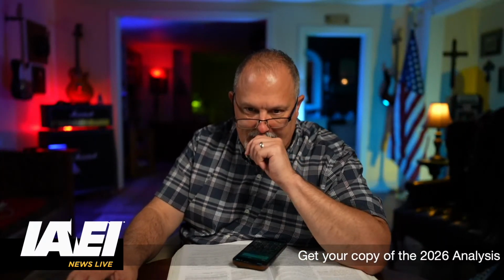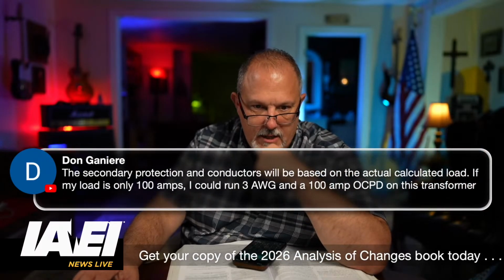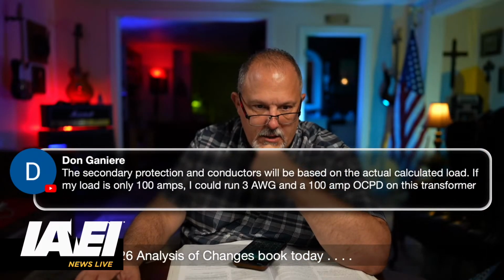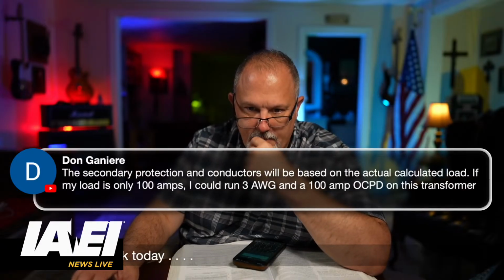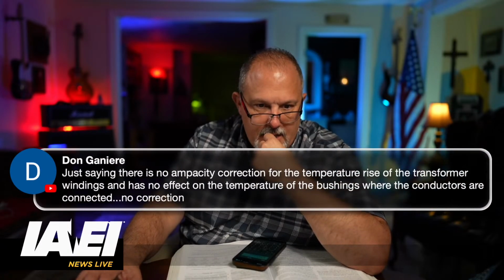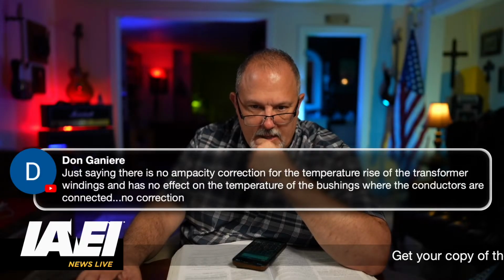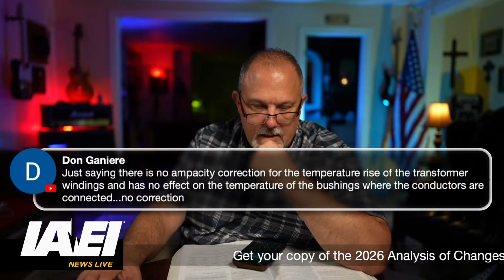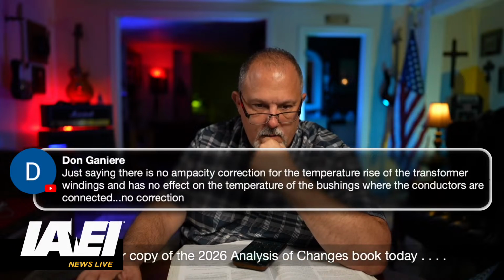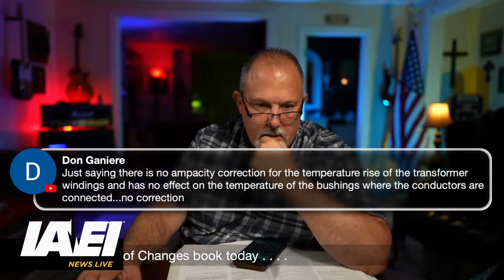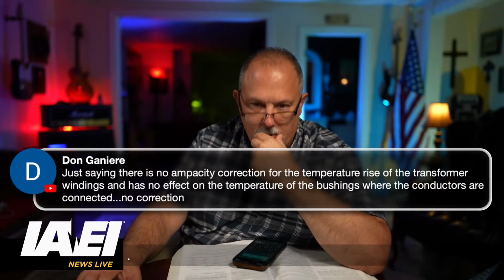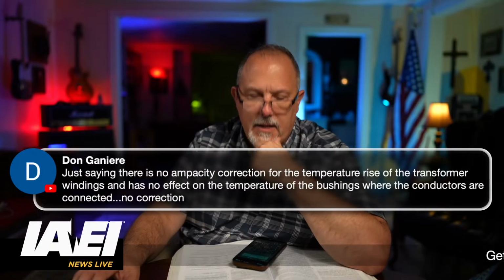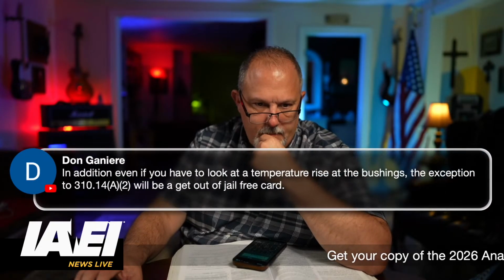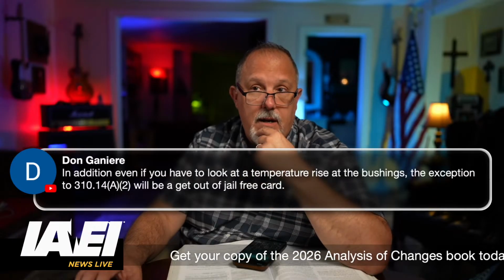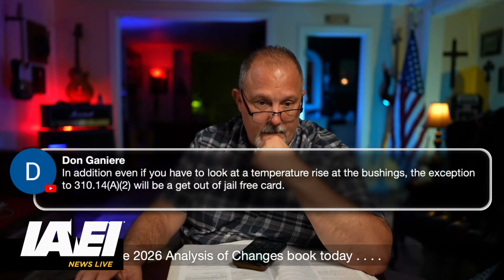All right, we got more comments. Dawn, back at it again. The secondary protection and conductors will be based on the actual calculated load. My load is, oh, we already said that. Sorry. Just saying there is no ampacity correction for the temperature rise of the transformer windings. I didn't say there was. I'm good with that. I agree with you. Bushings where the conductor is connected, no correction. I agree. I don't think I implied there would be, but if I did, then I agree with what Dawn was just saying.